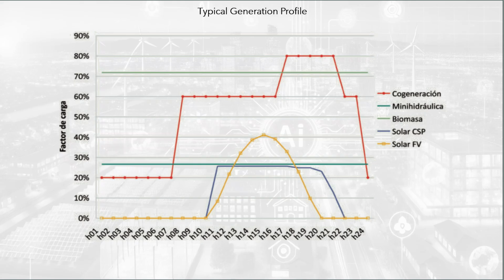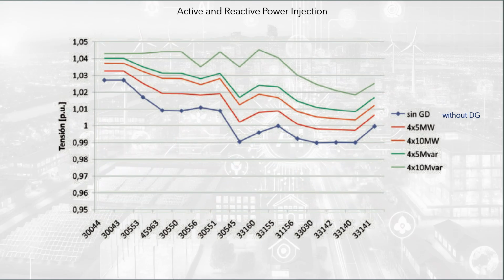The figure presents the typical generation profile of the different renewable technologies and cogeneration. DG technologies vary depending on the voltage level, so it has been assumed that in DG networks, high voltage, HV, 132 to 45 kV, the predominant generation is wind and cogeneration, medium voltage, MV, cogeneration, solar photovoltaic and mini hydro, and in low voltage, LV, solar photovoltaic. For the analysis, different typical profiles by technology have been used. The horizontal axis is in the hours of a typical day. The acronym SIN-GD stands for without distributed generation.